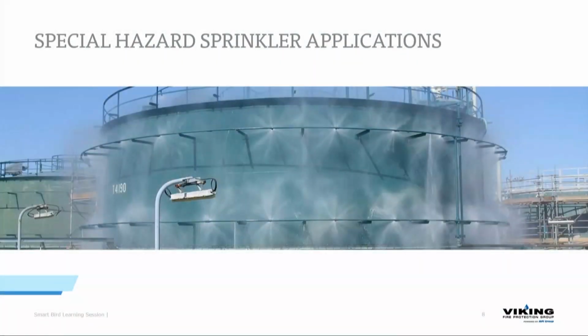All right, now we're going to leave a little bit of the life safety behind us and talk about life safety and mechanical safety. Now we're into protecting equipment, protecting tanks, protecting other things that might have a special need. So right here we've got a great looking deluge system on a chemical storage tank, UV detection on the sides, 10 by 10 pattern or 10 by 12 pattern, fully coating the entire exterior of this chemical storage tank.